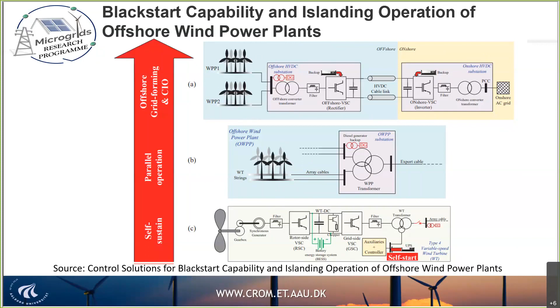The next level is the parallel operation of all those systems, together with the grid and between them. The next level is to have grid forming offshore systems, some connected in parallel, able to form a grid. From the DC side you could also connect to AC—they work a lot on DC, but it's possible to export to AC as well. This is one example from our colleagues in Valencia working on this project.